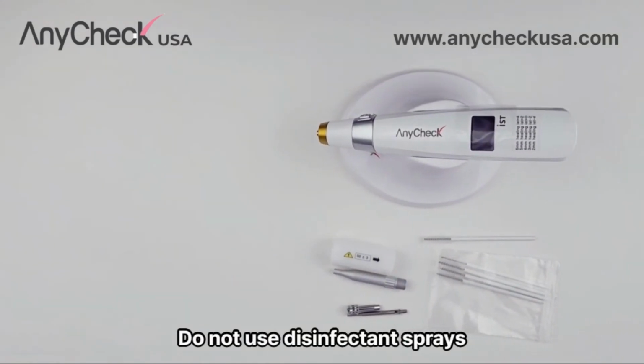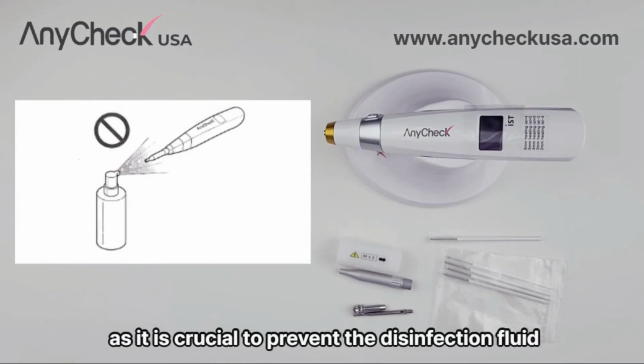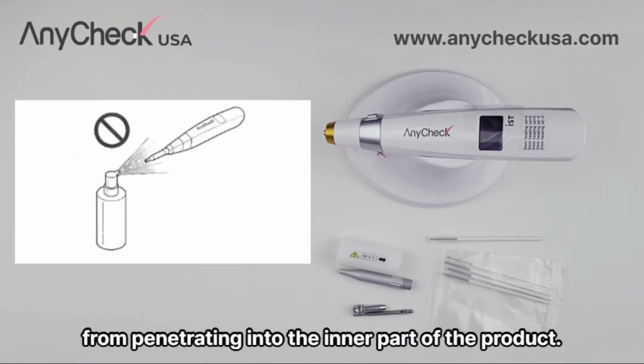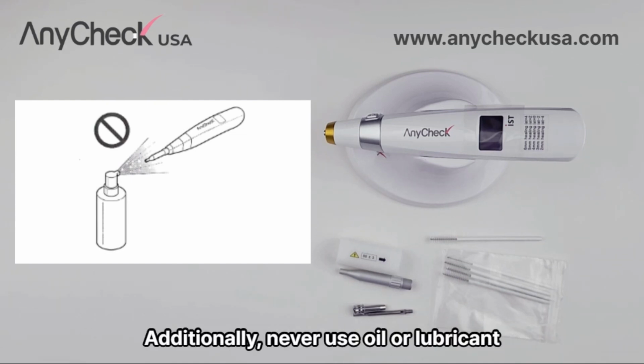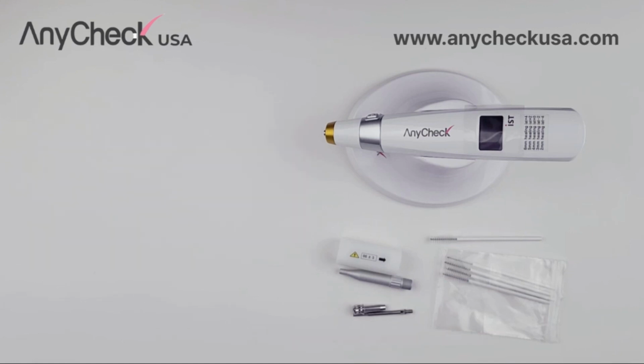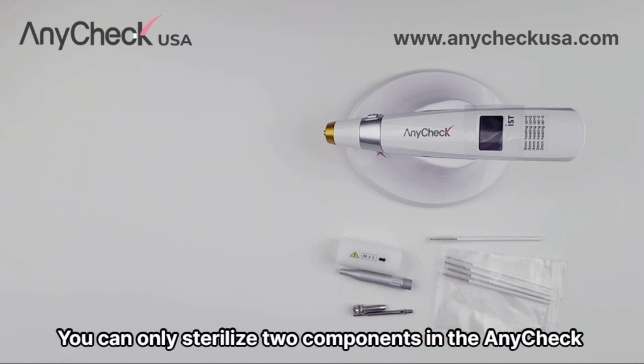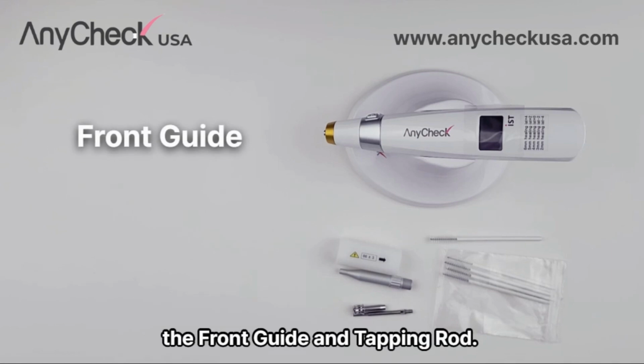Do not use disinfectant sprays as it is crucial to prevent the disinfection fluid from penetrating into the inner part of the product. Additionally, never use oil or lubricant. You can only sterilize two components in the Anycheck, the front guide and tapping rod.